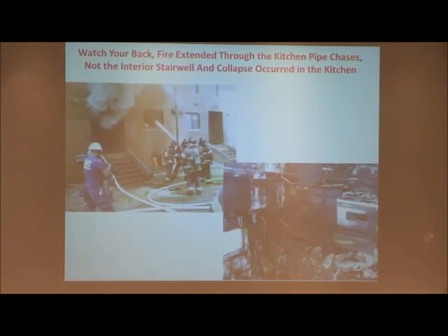One of the challenges here is the thought that the fire is going to come up the stairs. In many cases, coming up the stairs may not be the path of least resistance. In these fires, typically what happened is the fire came up the pipe chases into the kitchen and flashed over the kitchen and dropped the kitchen floor.